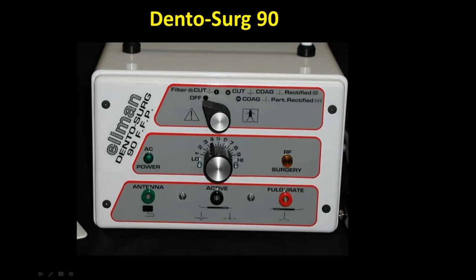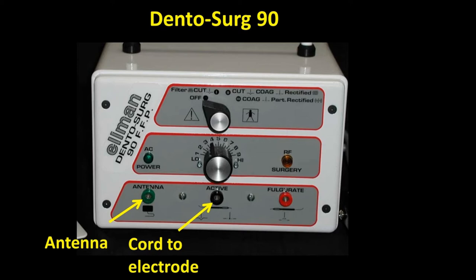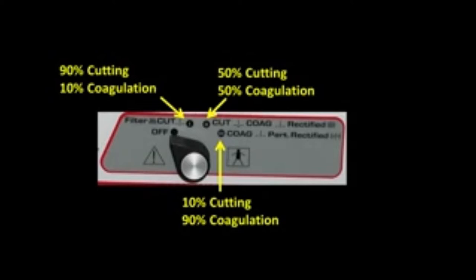The Dento-Surg 90 unit came on the market in the late 1960s and was developed by Dr. Ellman. There are two ports on the bottom of this unit — the first port takes the cord that attaches to the antenna, and the second port is the cord that leads to the cutting tip. What I like about this unit is it has multiple settings. You can see we have a fully filtered cut on the left, which is the one we mainly use.